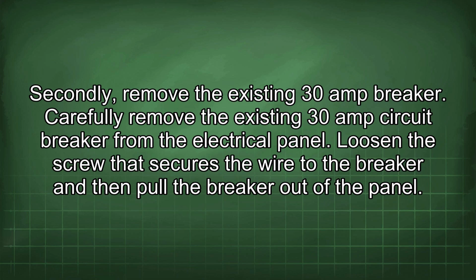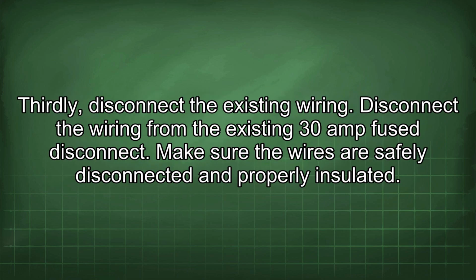Secondly, remove the existing 30 amp breaker. Carefully remove the existing 30 amp circuit breaker from the electrical panel. Loosen the screw that secures the wire to the breaker and then pull the breaker out of the panel. Thirdly, disconnect the existing wiring. Disconnect the wiring from the existing 30 amp fuse disconnect. Make sure the wires are safely disconnected and properly insulated.